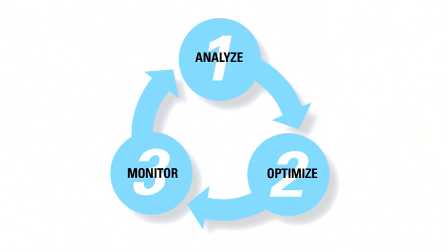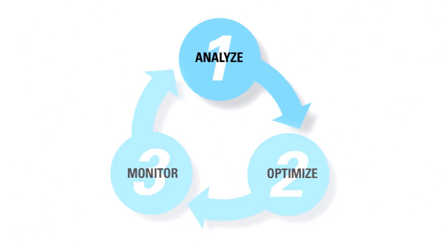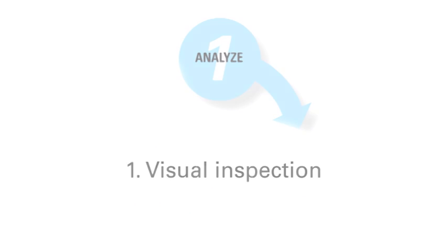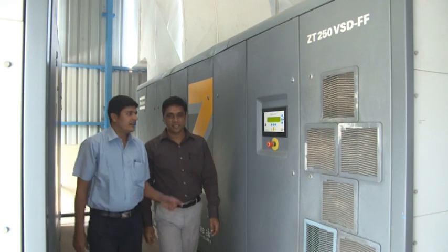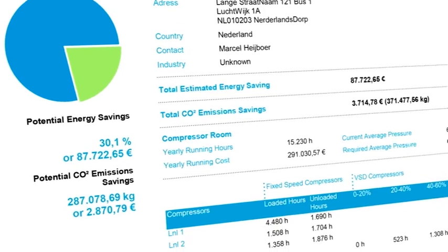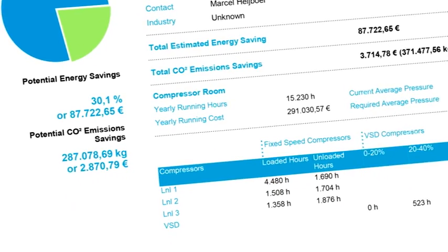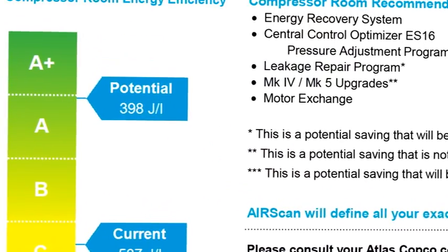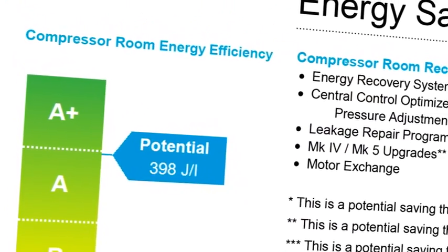The first step to optimize the compressed air system is to analyze the actual situation, typically done in two sub-steps. Visual inspection is the first sub-step. By looking at load patterns, the pipe work, the receiver size and so on, we detect weak points in the installation and define potential areas of improvement. Already during a first inspection visit, our calculation tools, such as the energy potential calculator, enable us to estimate the potential savings.